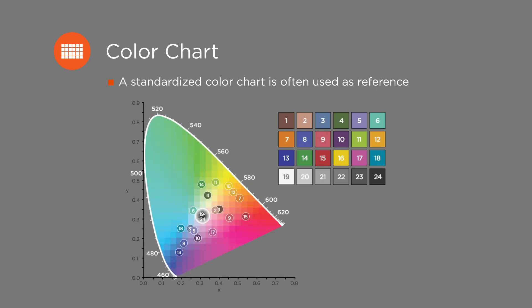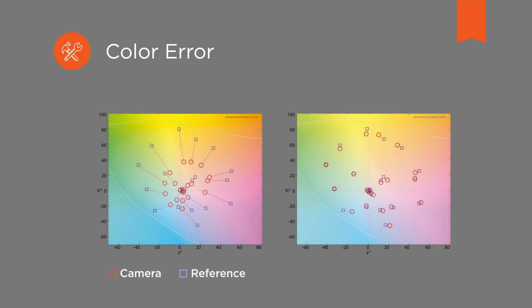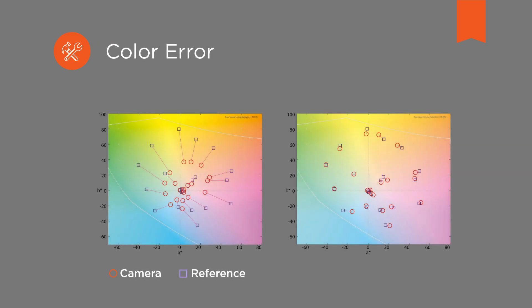For each color patch on the color chart, the camera supplies a color value, which is then compared with the target color value provided together with the color chart. The difference between these two values is the color error delta E. The aim of the calibration process is to set parameters in the camera to minimize the color error for all colors.